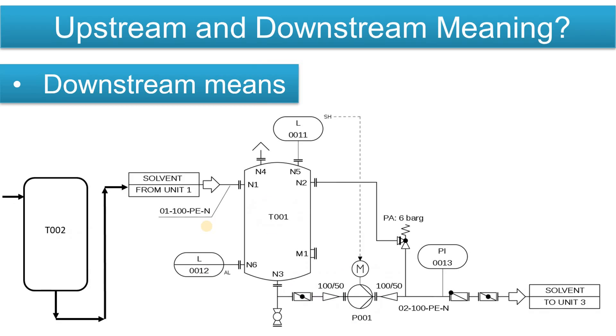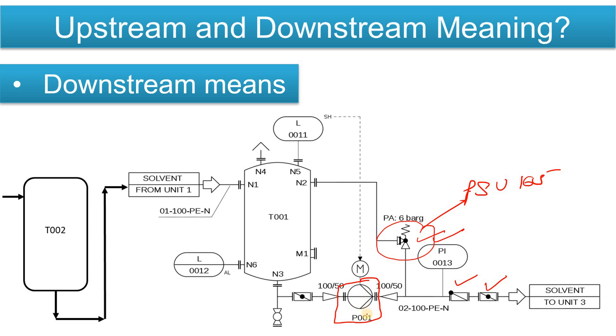Now what will be the downstream? The downstream means everything after the pump: the dampener, the pressure gauge, the safety valve, and the butterfly valve on the discharge side — all of these are downstream. For example, if I say please check whether the downstream PSV of P-001 — say PSV-165 — has popped up or not, or please check the reading of the downstream PG of P-001. This is the downstream PG, this is the downstream dampener, this is the downstream butterfly valve of P-001.